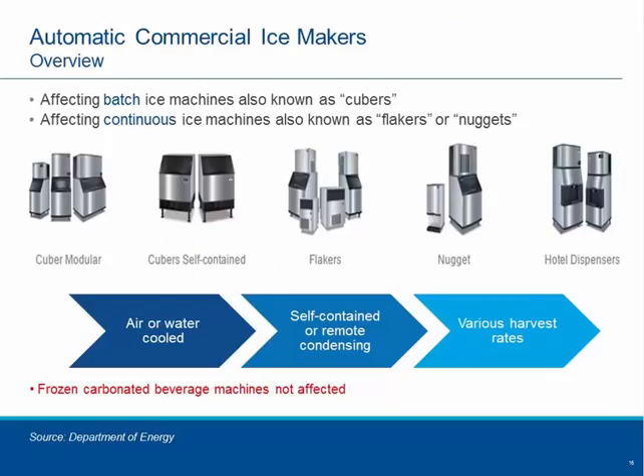Finally, the last overview is on automatic commercial ice makers. You can see that there are two different classes of equipment. You have batch machines, which are known as cubers. This is where the ice actually freezes on a plate, and through a hot gas defrost method straight from the compressor, you melt the ice a little bit off the plate and gravity forces it to fall.